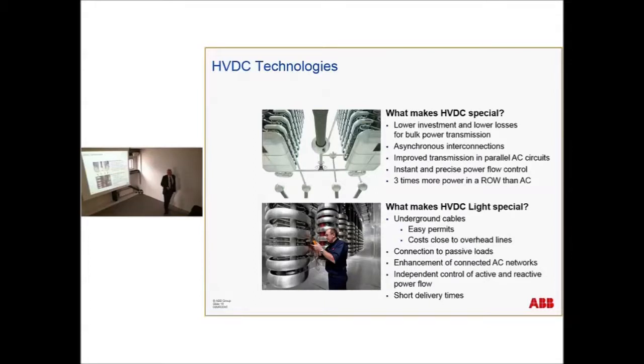So to summarize here the HVDC technology, what makes it special compared to AC? For long distances and high power, it's a lower investment and lower losses. You can connect asynchronous networks, and if you have what we call embedded parallel DC links with existing AC links, you can improve the stability and the transmission capability, since you can control the power flow. Thereby you can have a higher load angle, since you can control the power during disturbances, etc.